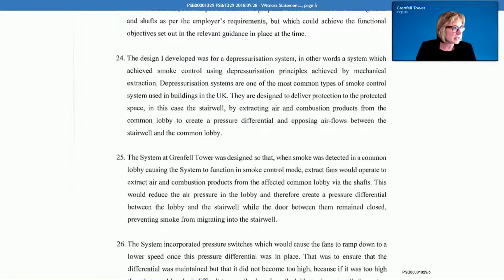He says this: the design I developed was for a depressurization system. In other words, a system which achieves smoke control using depressurization principles, achieved by mechanical extraction. Depressurization systems are one of the most common types of smoke control system used in buildings in the UK. They are designed to deliver protection to the protected space, in this case the stairwell, by extracting air and combustion products from the common lobby to create a pressure differential and opposing airflows between the stairwell and the common lobby.